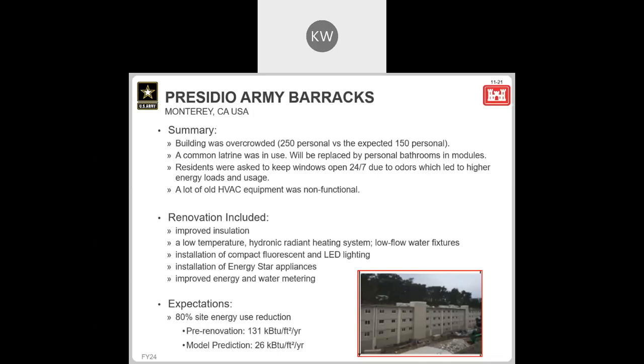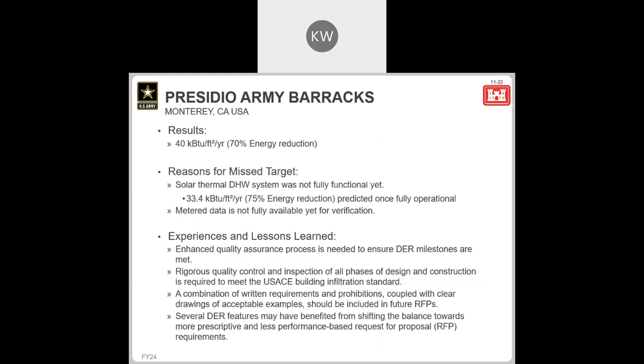So they were targeting an 80% site energy use reduction. They had 131 kBTU per square foot per year as their baseline, and they're hoping to go to 26. The results, as of when this document was posted, were showing 40 kBTU, which was a 70% reduction. So they didn't quite hit the target fully, but that was still a great one. If 50% is what we're going to use to define deep energy retrofit, then they well cleared that hurdle.